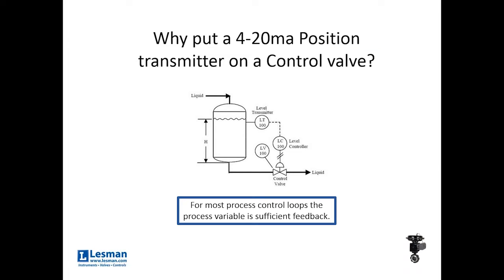In a typical control loop, the feedback is the process variable. The control system decides to make a change and moves a primary element like a valve. The valve changes flow or pressure, which is then picked up by a pressure transmitter, temperature transmitter, level transmitter, or some other instrument measuring the process variable. It's a closed loop: you make a change, the change happens, and some instrument detects the change.